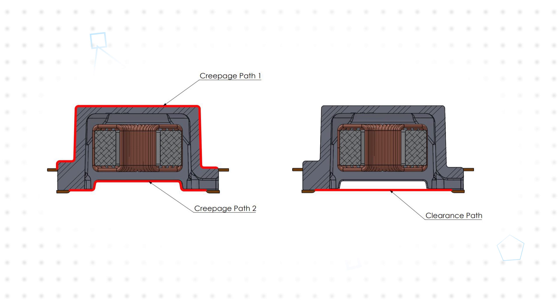One of the challenges of working with high voltages is meeting the creepage and clearance requirements while simultaneously minimizing the design size. The HCTSM110103HAL features a toroidal core, which provides good coupling between windings with minimal radiation, allowing for fewer turns to be used. It also eliminates the coil former for additional space savings, and is fully sealed, eliminating exposed areas that reduce clearance. This also maximizes the creepage path.